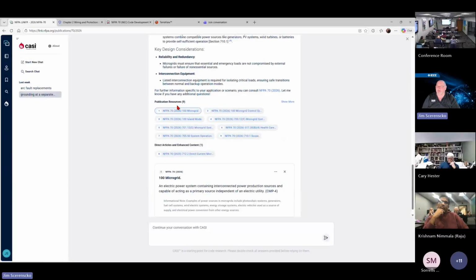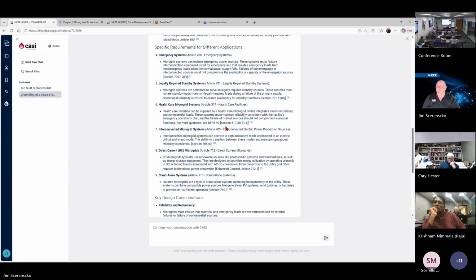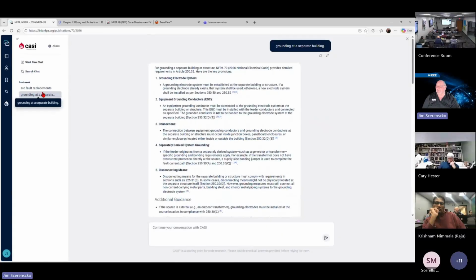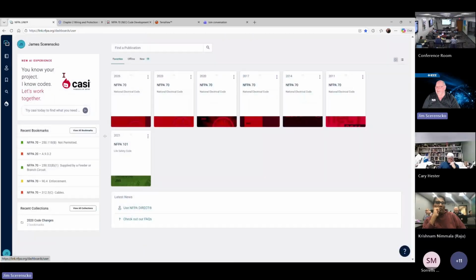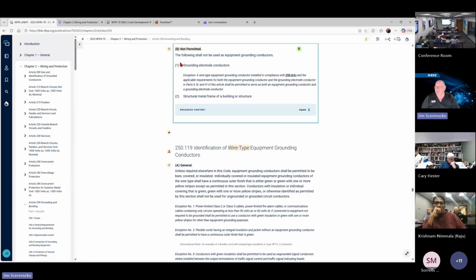So yes, they have incorporated it, and this is the first year that we've had this AI stuff in here. We've always had search, and we've always had bookmarks, and what you bookmark in 1 year carries over to the next year. So I bookmarked this, 250.118B, which is not permitted to use a grounding electrode. Then there's an exception for the secondary side of transformers, which is almost impossible to make code compliant.